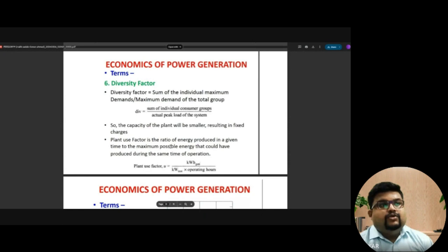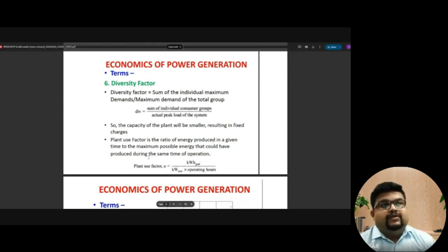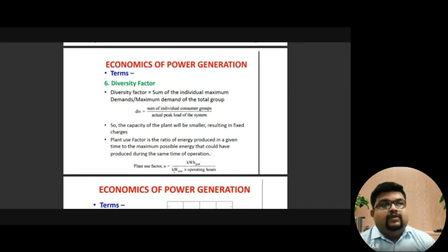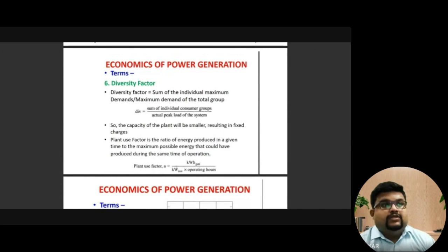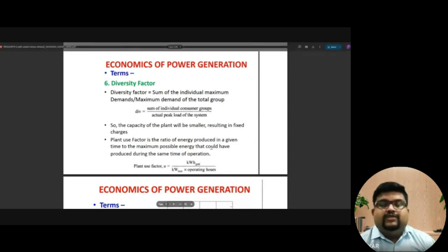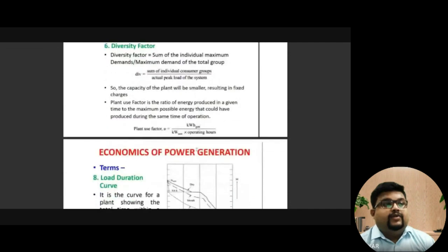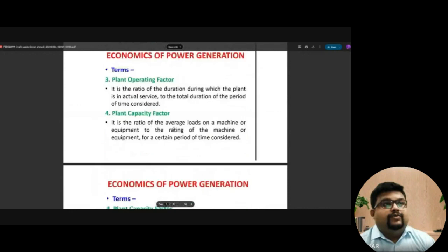Plant use factor is the ratio of energy produced in a given time to the maximum possible energy that could have been produced during the same time of operation. It considers the KWH which are generated — the work being done in KW for a number of hours. This formula tells you what percentage of its original capacity the plant is being used for.